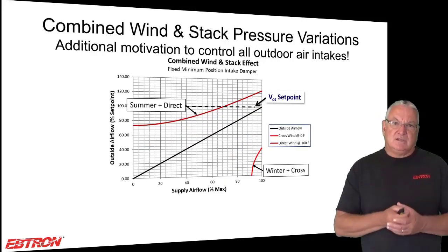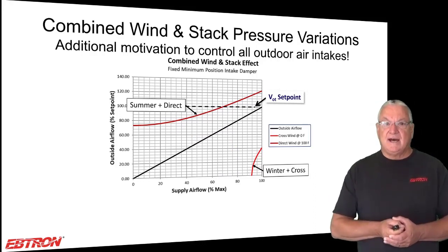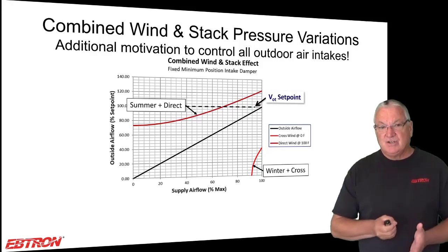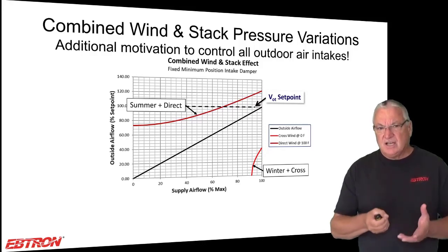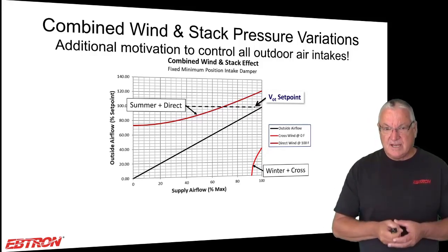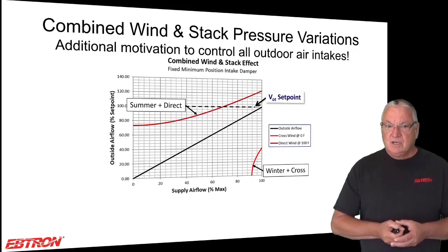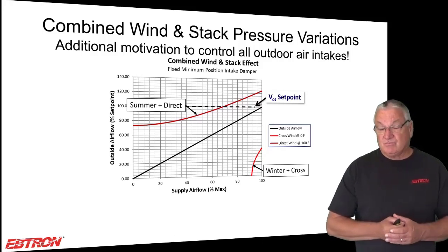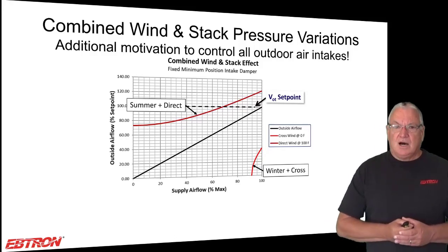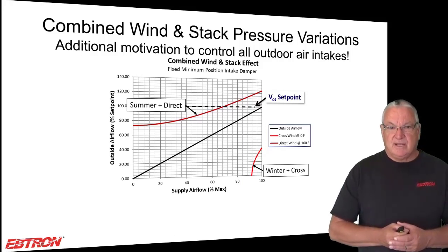And of course, the reality is that you don't just have wind or stack, you have a combination of the two. And when you look at it that way, you realize that if you just rely on fixed damper positions, or even multiple fixed damper positions, which I'm going to show you is even worse, you don't really know how much outdoor air you have coming in.